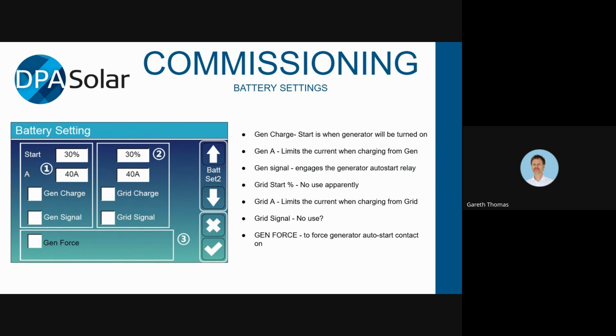And then the current limits the amount of current when charging from the generator. Gen charge needs to be enabled for that to happen, and gen signal needs to be enabled if you want to use the 2-wire auto start functionality. On the right-hand side here, you've got the grid charge section. According to the manual, grid start percentage has no use. And this value here, again, is going to limit the amount of current when charging from the grid.